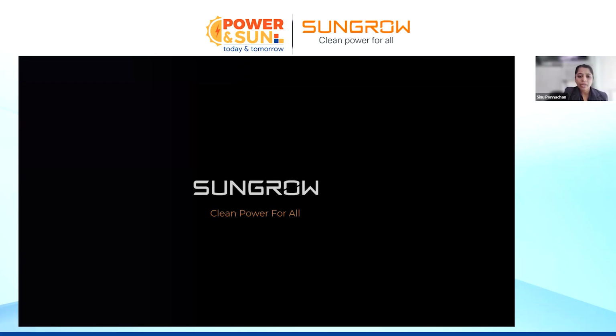Jay Mehta. He is mentioning, in case of DC coupled system, is it possible to configure it to work as a zero grid export system? Yes, absolutely. So whether it's DC coupled or AC coupled, Jay, we can enable the zero export. So what we do, we install a power meter on the load, and this power meter, for example, in the DC coupled, will be connected to the logger or to the inverter directly. It will read whatever the load is consuming and tell the inverter, okay, just produce accordingly. Nothing extra will be produced. Therefore, this is a zero grid export application.